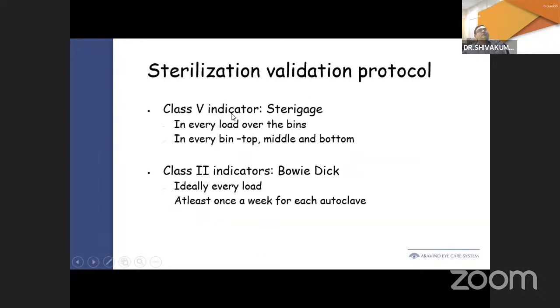The class 5 indicator Sterigage, which we saw, is placed in every load over the bins in every cycle, and in every bin at the top, middle, and bottom to ensure proper sterilization throughout the bin. And class 2 indicators should be there for ideally every load, the Bowie-Dick test as it is called, and at least once a week for each autoclave so that we know that it is functioning well.